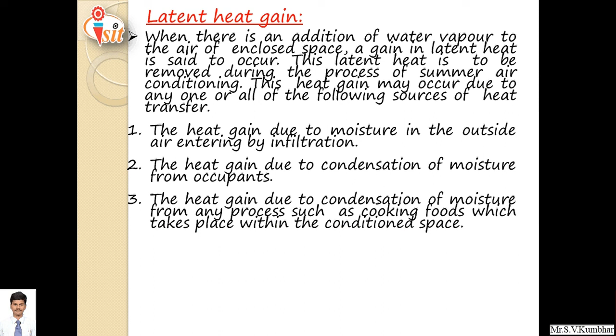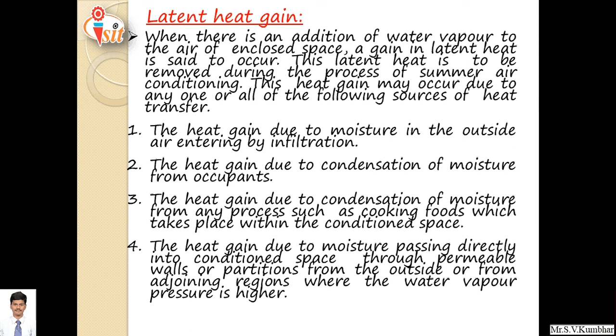Third one, the heat gain due to condensation of moisture from any process such as cooking food, which takes place in the kitchen, and that has to be considered within the conditioned space if it is coming under that conditioned space. Fourth important parameter, the heat gain due to moisture passing directly into conditioned space through permeable wall and partition from outside or from an adjoining region where the water vapor pressure is higher.